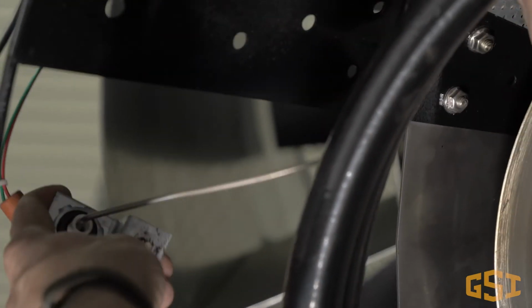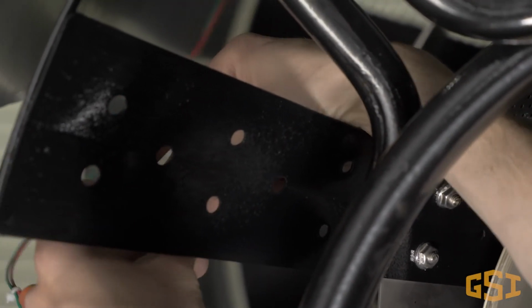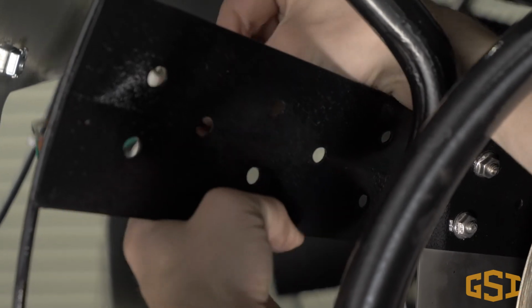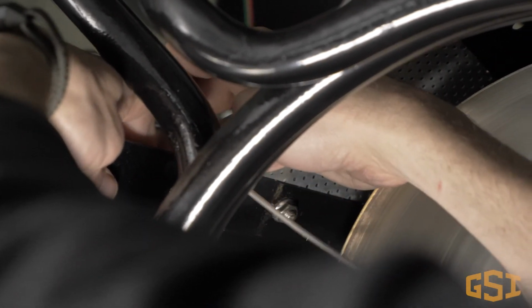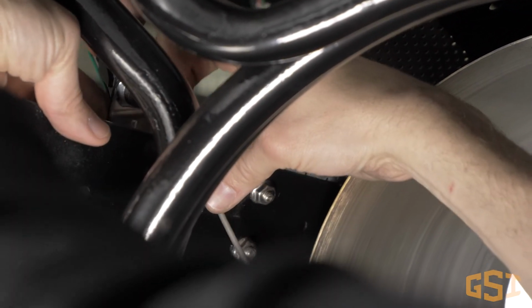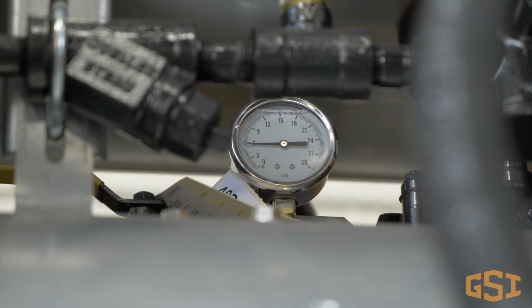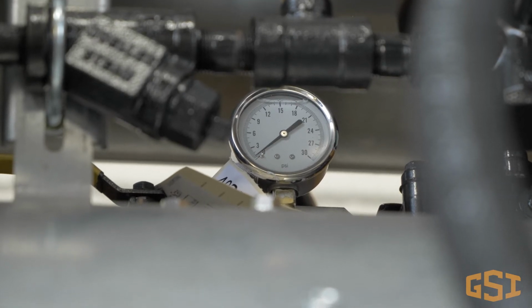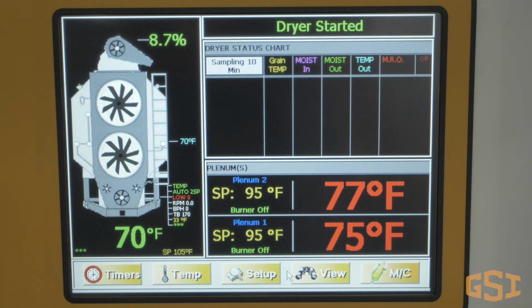Make a change and then relight the burner. Watch the burner light. If the light blinks or goes out entirely, you should shut down the dryer and reposition the flame probe. It may take a few attempts to reposition the flame rod before you get it in the location that contacts flame all of the time. Now that you have a basic understanding of how flame rectification works, let's look at ways to help guide you as you position the flame probe.